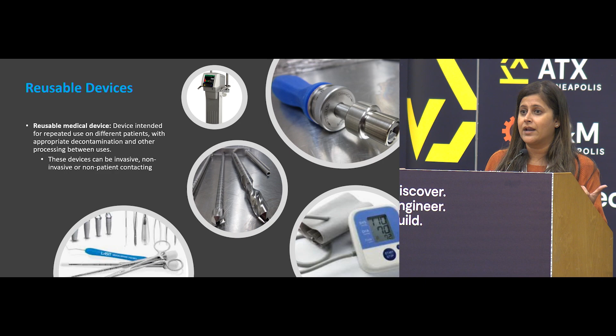But I also wanted to bring an emphasis that when we're talking reusable, we're also talking about non-critical devices. These are devices that are not patient contacting, or they are patient contacting, but only with intact skin. So during the presentation, you will see that I do cross over from critical to semi-critical to non-critical, and these are different categories of devices that are utilized for validation plans. And why am I focused on cleaning? Because these devices here that you'll see the yellow spot on, they have hospital practices, right? There are organizations in healthcare facilities that do write procedures to clean these type of devices.